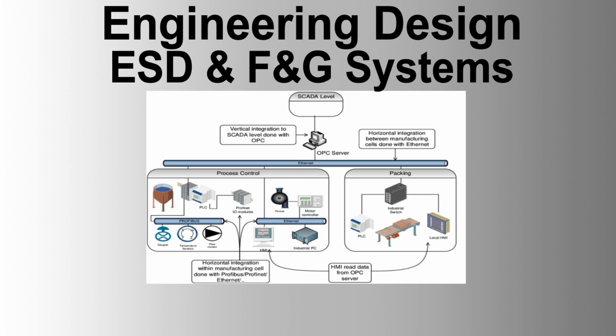Emergency shutdown system, ESD. 1. Monitoring and control. The ESD system shall monitor all areas for process conditions outside the normal range of control. It shall automatically protect personnel, equipment, and the environment by initiating appropriate alarms and shutting down the plant either partially or fully as per cause and effect sheets.